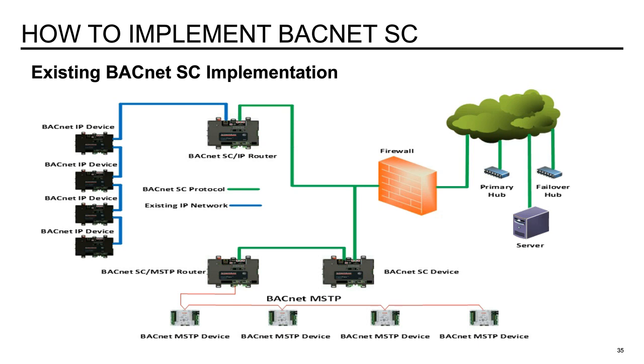Okay, our next question is from Zahir. If any device fails for any reason on a BACnet SC network, what will be the impact on the other devices on the same network? So the BACnet SC devices will continue to communicate with each other, and the devices that are behind the BACnet SC router would continue to function in a standalone methodology without connection to an upper level controller or to the server, if you will. But in the case of what's on my screen, right here on your screen, if one of these BACnet SC devices were to stop talking, the other devices would continue to talk.